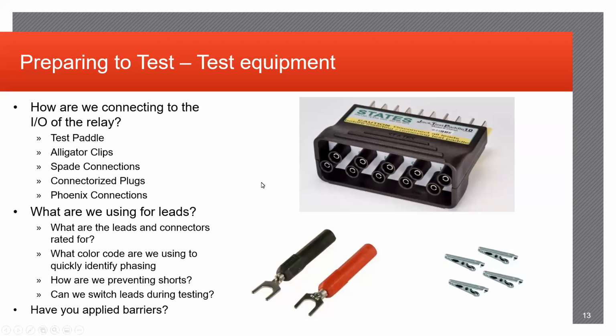As well, when you're connecting to the relay, some of the spare outputs that you may be utilizing for testing purposes may not be connected to the knife switches, in which case you'll just be going directly to the back of the relay and screwing in some of these spade connections directly to the back of the relay for testing purposes.